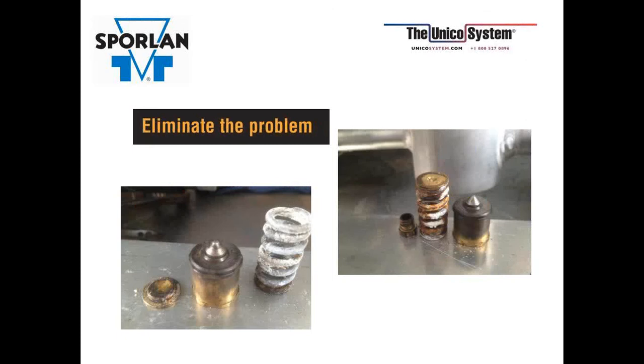And this is a real-world situation where I took these pictures myself. These were OEM installed, not by Unico. This is from a big OEM for a produce cooler. But you notice the discoloration on the pin and carrier. You also notice some sludge on the pin itself. The biggest thing that jumps out at you is the rust on the springs.